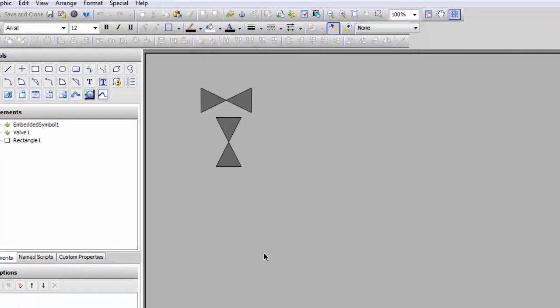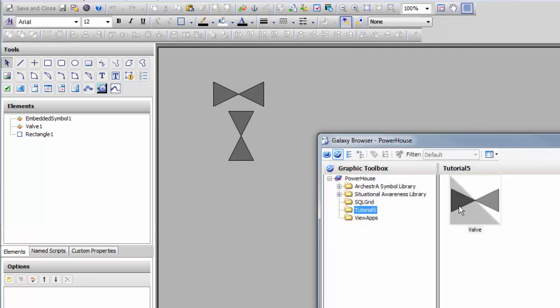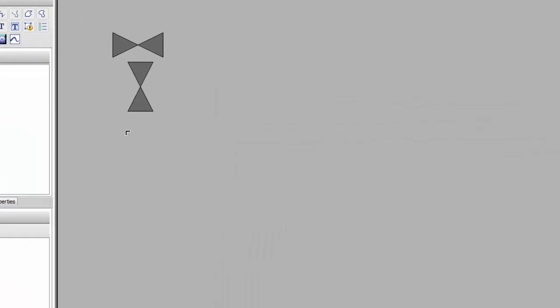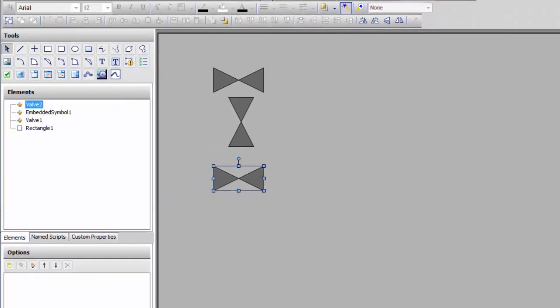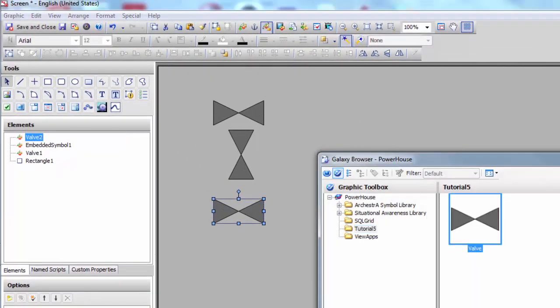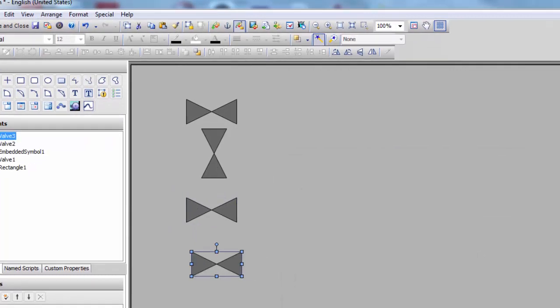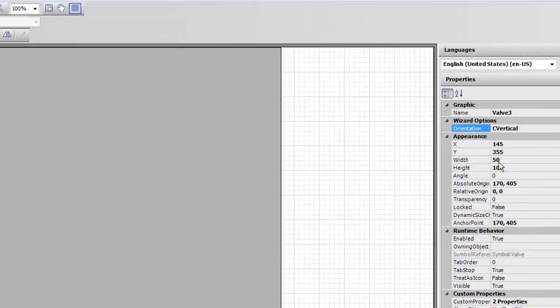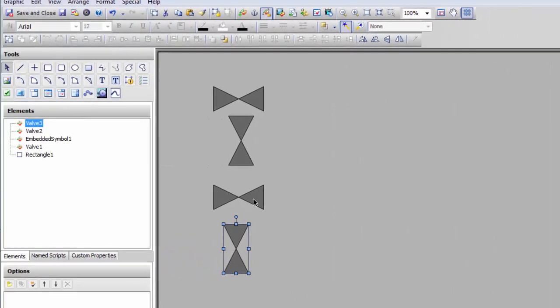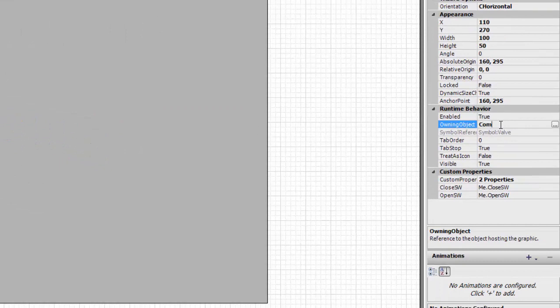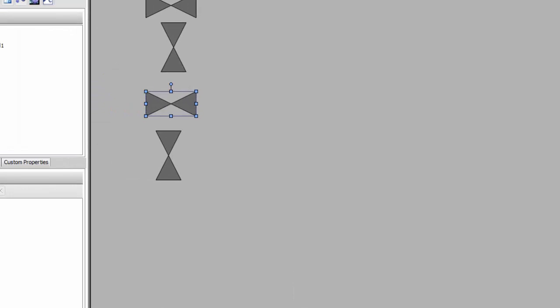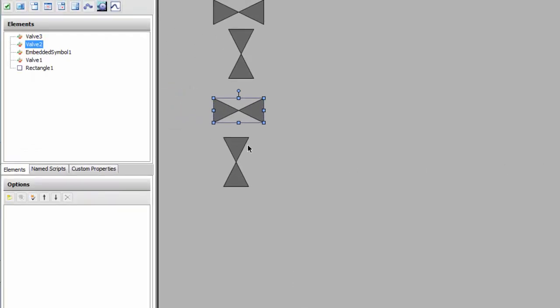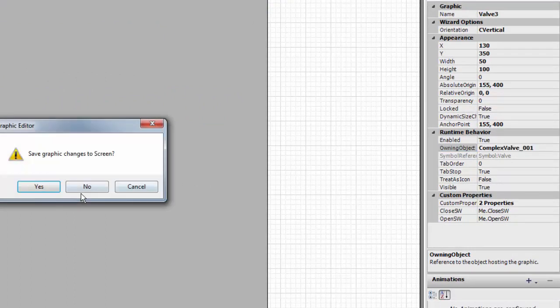Let's go to the screen. This is a screen graphic that's actually embedded in the view app. We can either select this by using our embed graphic option or we can just copy and paste one of these. I'm going to go ahead and use the embed option. That's a horizontal so let's make that our complex horizontal. Then let's grab another one and make that our complex vertical. These guys are going to need the complex valve 001 I believe is the name. We've got to set our owning object to the correct object in the galaxy and now we should be good to go.